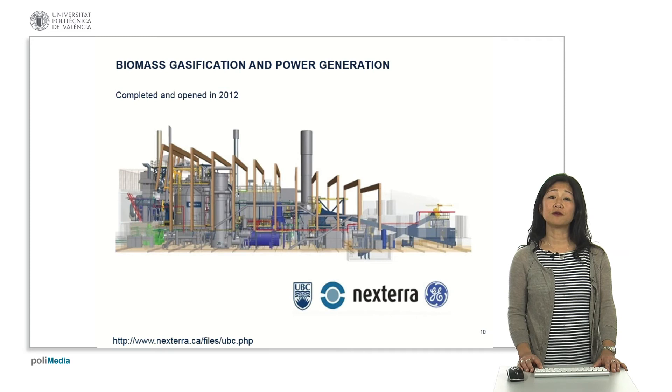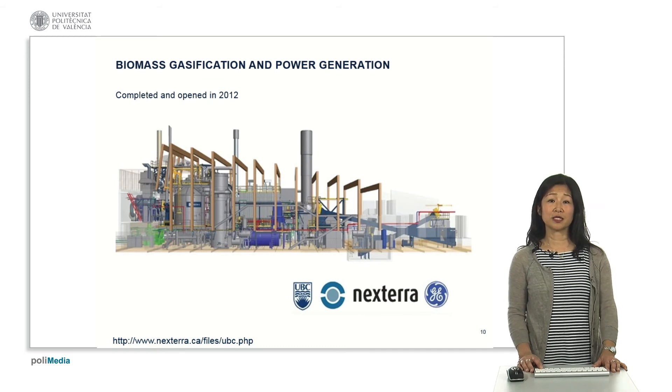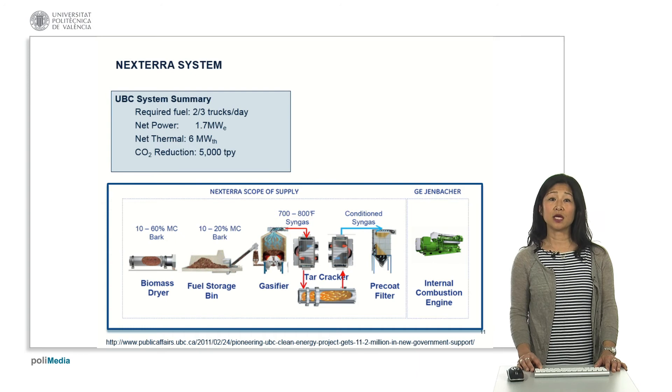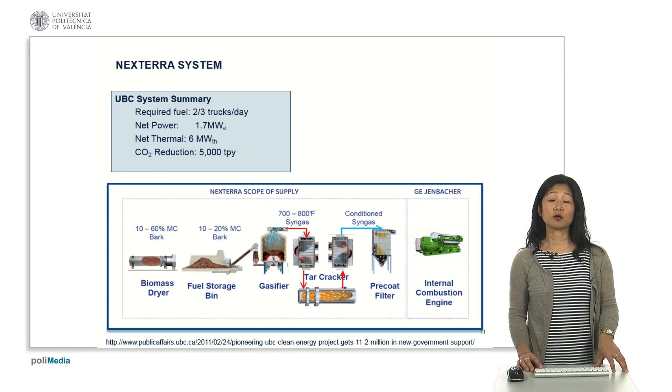The biomass gasification unit itself is provided by a local company called Nexterra, which has an air-gasified updraft gasification system on campus. The Nexterra system requires two or three truckloads of fuel per day to be delivered — biomass waste streams collected within a 120-kilometer diameter of the campus. The net thermal energy output is six megawatt thermal, and when working with the internal combustion engine, we were able to provide 1.7 megawatt electrical.